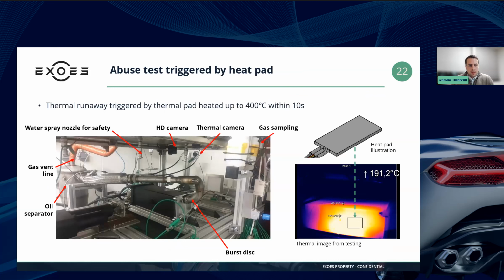Just to give you a better understanding of the test setup, here you can see the module sitting on the bench. It's painted black for the thermal image recording. You can see piping, an exhaust line effectively, that is connected to a burst disc or a pressure relief valve that feeds into an oil separator, and then into a gas vent line that is connected to a filtration system. We also have safety features like a water spray nozzle.